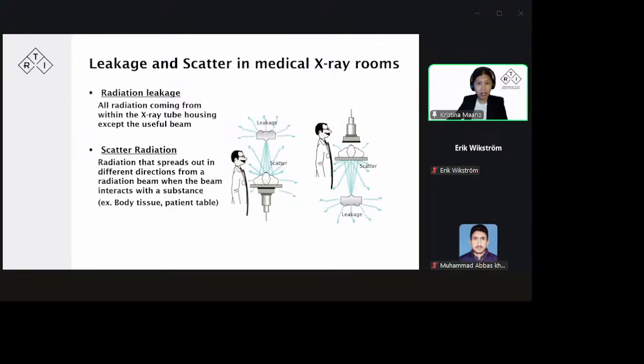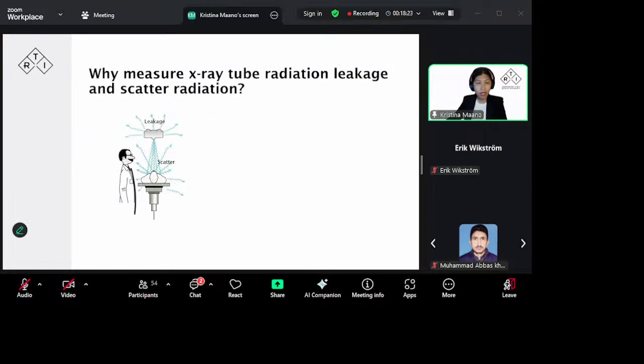And how about scatter now? Scatter radiation is different from the leakage radiation. Scatter radiation originates from the patient's body after the primary X-ray beam interacts with the substance. Now, a substance can either be the patient's body or the imaging table. And in a typical diagnostic imaging procedure, both types of stray radiation are present. So why is it important for us to measure the X-ray tube radiation leakage and scatter radiation? Both of these contribute to the unnecessary radiation dose to the patient and the staff.